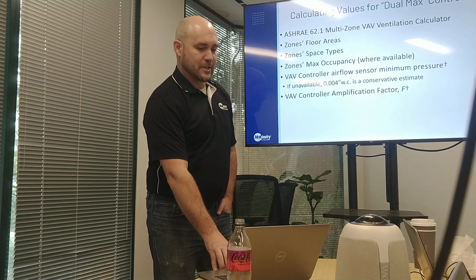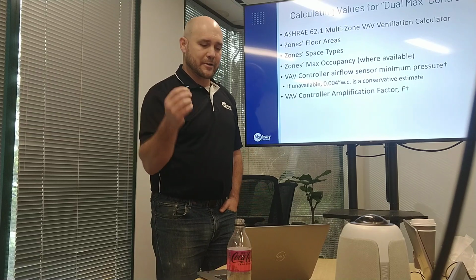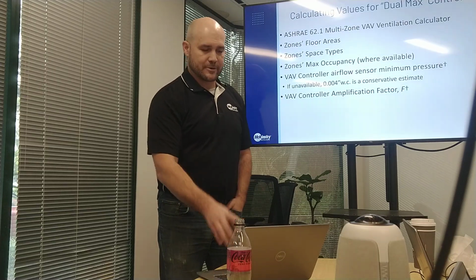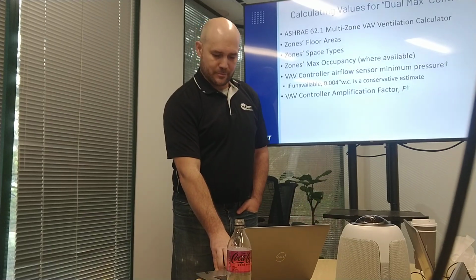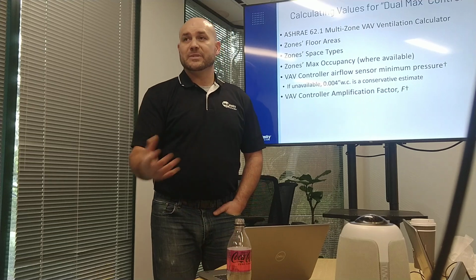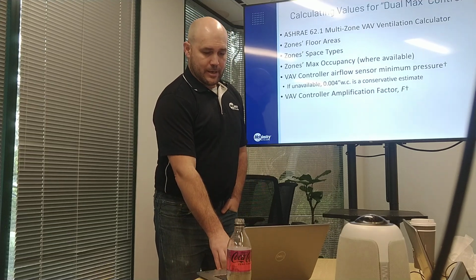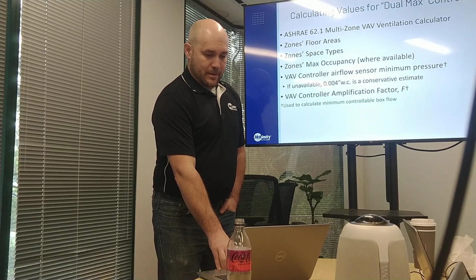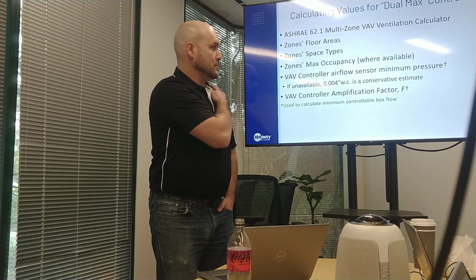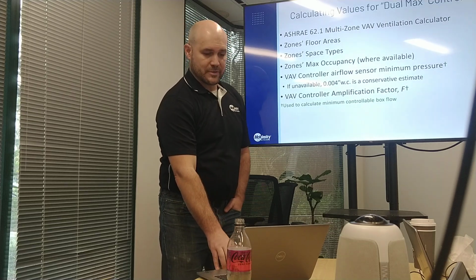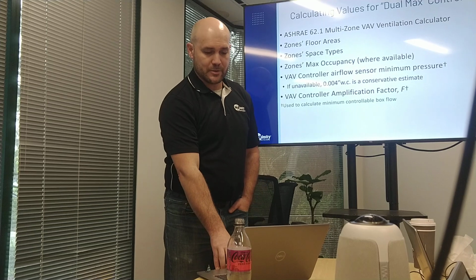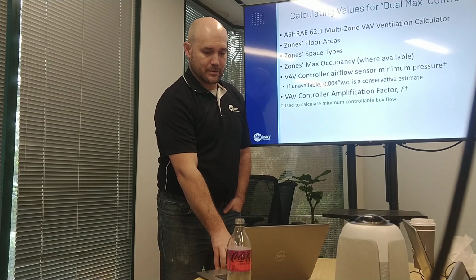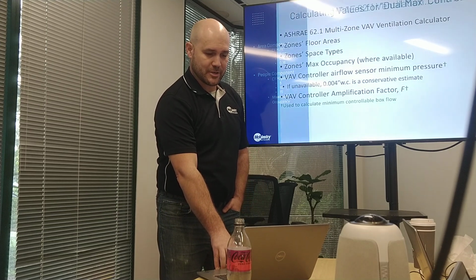There we go. So then there's this other variable that's inherent in the controller. It's called the amplification factor, usually indicated by F. If that's not given, we can calculate it. And these last two items here are used to calculate the minimum controllable box flow, which is going to be also a big limitation or big consideration in all this.